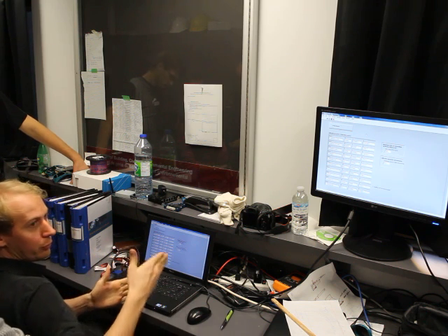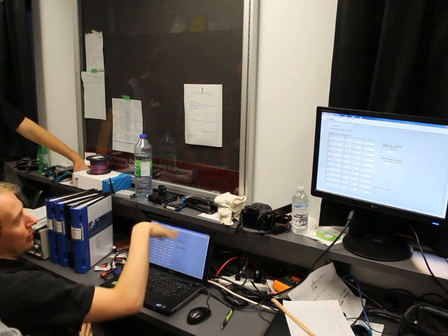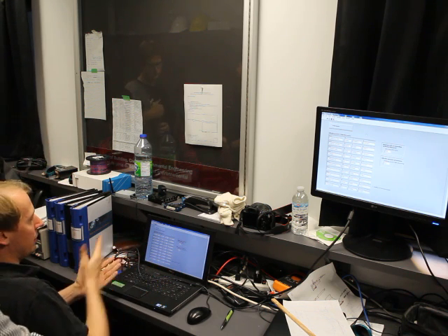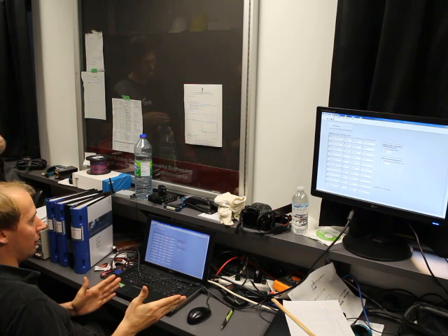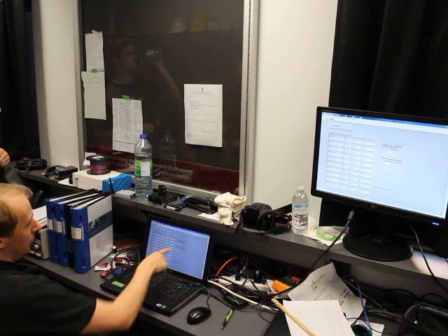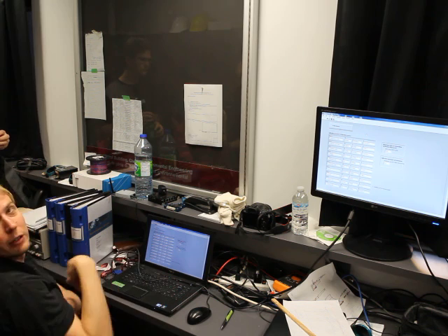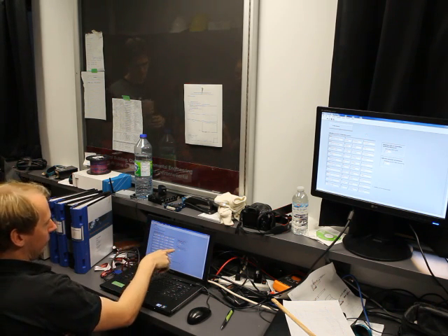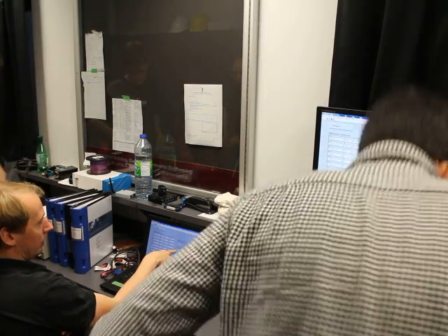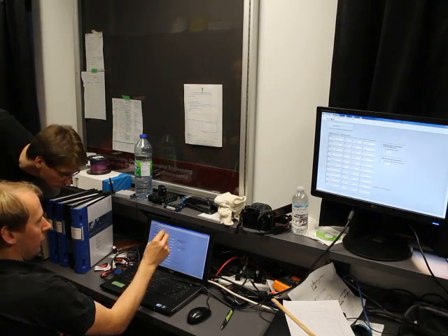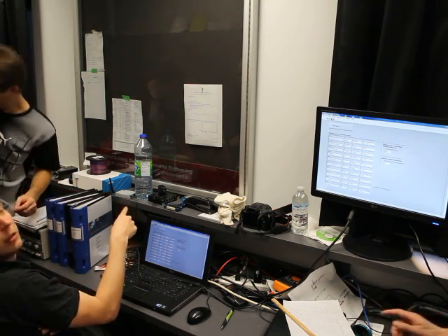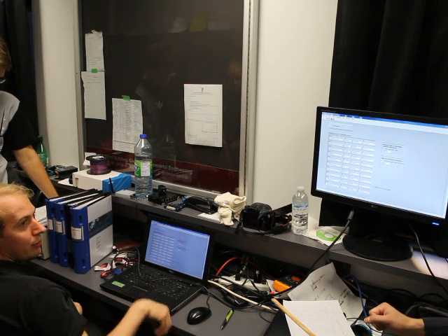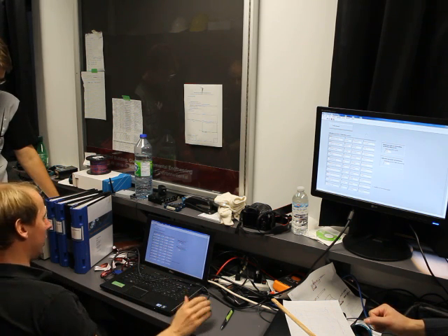With 4 to 20 milliamps, you can change the range of the flow sensor. At the moment it's 0 to 1000 liters per hour. So if you would change that to 1200, you should type that in here. Otherwise you will get wrong values. And for the calibration parameter for the pyranometer, that's 9.24 at the moment, which is in there. If you recalibrate that, you will get a new sensitivity for the pyranometer. You can add that here.